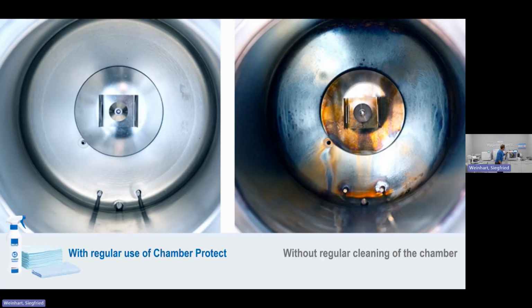Look after your internal chamber. What we want from our chamber is something like this. Okay, what can happen is the image you see there on the right. We can get a lot of tarnishing happening inside of that chamber. So using something like Chamber Protect, which is a MELAG product, you can use this on any sterilizer. The idea with this is once a week you would take all that internal furniture out, non-linting cloth, and you get a microfiber cloth with it as well. Spray into the cloth, and then you're wiping around that entire chamber.